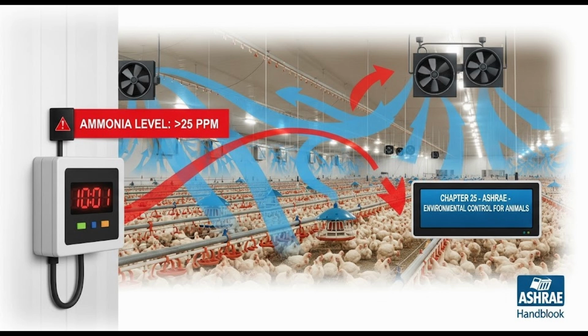Ideally, yes. But infiltration, unplanned air leakage through cracks and gaps, can really mess things up. There was a case study mentioned, Zhang and Barber 95. They measured infiltration in a swine building. What did they find? They found about 0.6 liters per second of leakage per square meter of building surface area at a typical operating pressure difference of 20 pascals, which doesn't sound like much, but it adds up. It added up to 1.4 air changes per hour just from leakage.